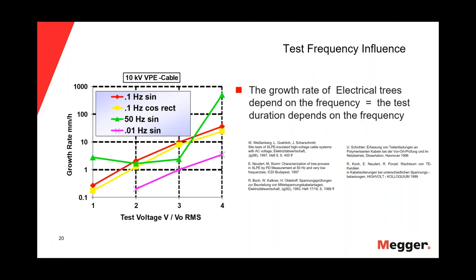Which means that if we decrease the frequency, we should extend the test time — otherwise we will not allow the electrical trees to convert to a fault. A practical approach: a VLF test at 0.1 Hz for 30 minutes produces 180 cycles. If we decrease the frequency to 0.01 Hz in 30 minutes, we will have only 18 cycles — 10 times less. That is the reason why if we decrease the frequency, we should increase the test time of the VLF test.